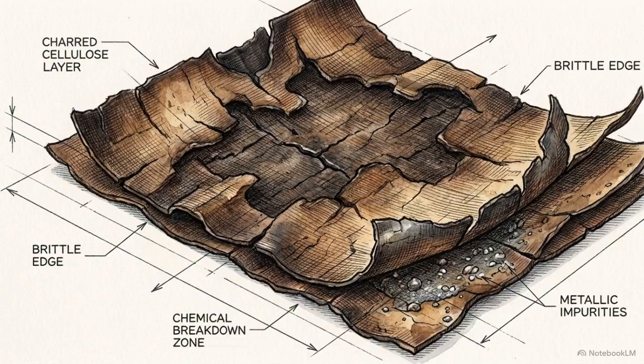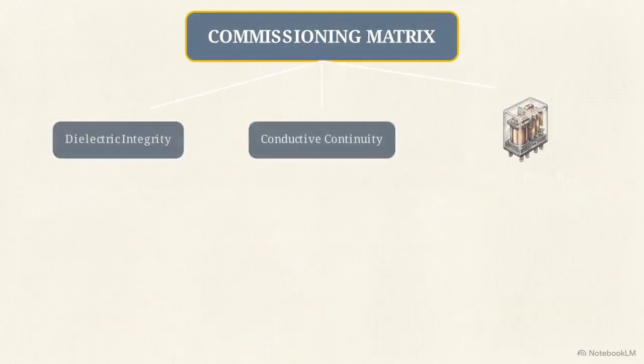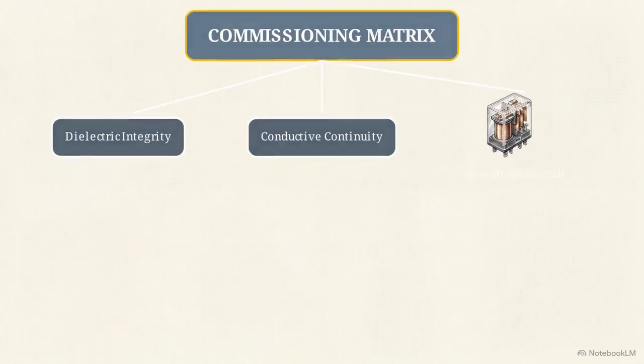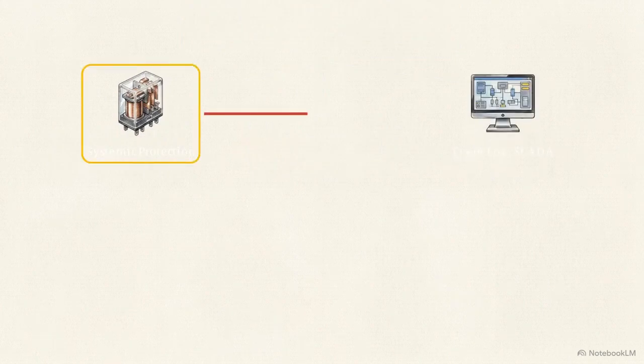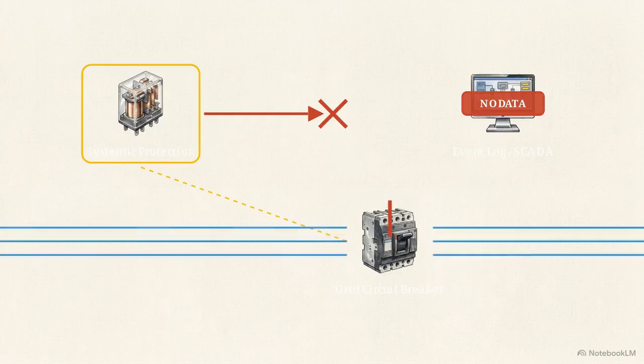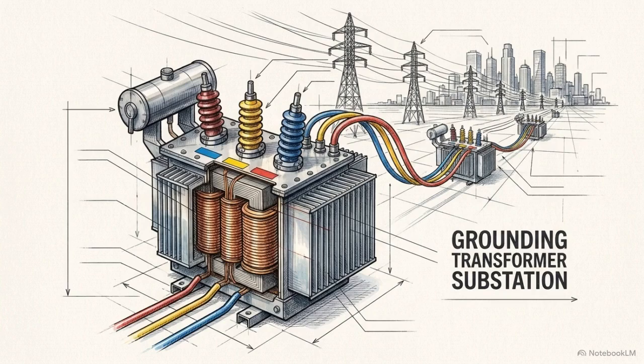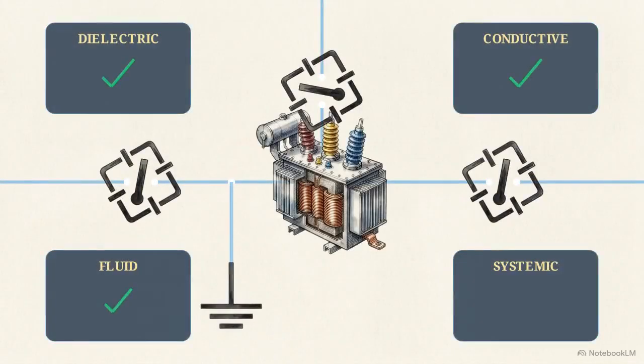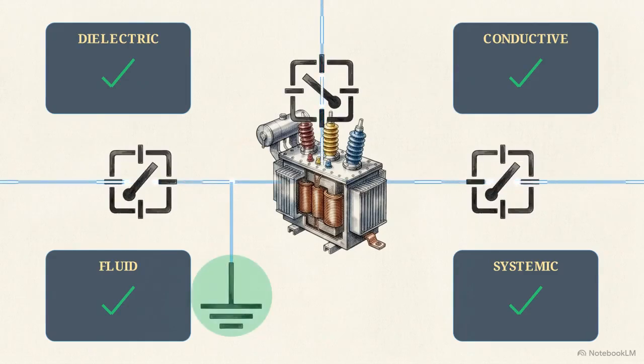The final diagnostic barrier is protection logic misalignment. If a physical trip at the marshalling kiosk fails to generate an event log on the remote workstation, engineers mandate an absolute block on grid energization. The grounding transformer gives the wider electrical grid its ultimate safety net. This exhaustive, multi-domain testing matrix is the only way to ensure the net itself has no holes.